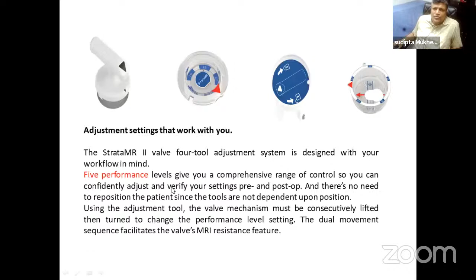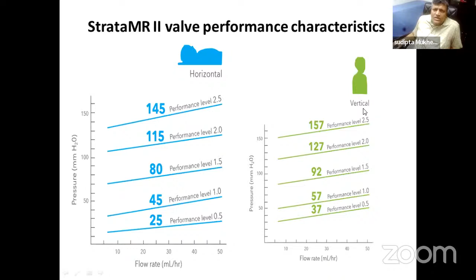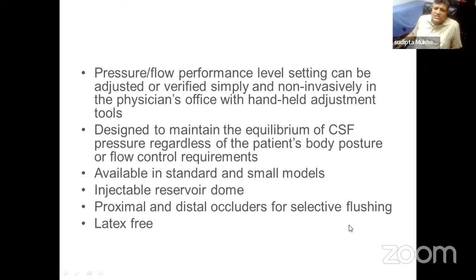See, what is the significance of a flow control valve? In a flow control valve where no programming is possible, it works on a single graph. But in this case, you see there are 5 graphs, so the patient can use a different graph as per necessity, and there are different graphs for horizontal or vertical position also. So the pressure flow performance level setting can be adjusted, designed to maintain equilibrium of CSF pressure, available in standard and small models. Injection can be given through the reservoir dome as well as CSF can be collected. Proximal and distal occluders are present and it is latex free.